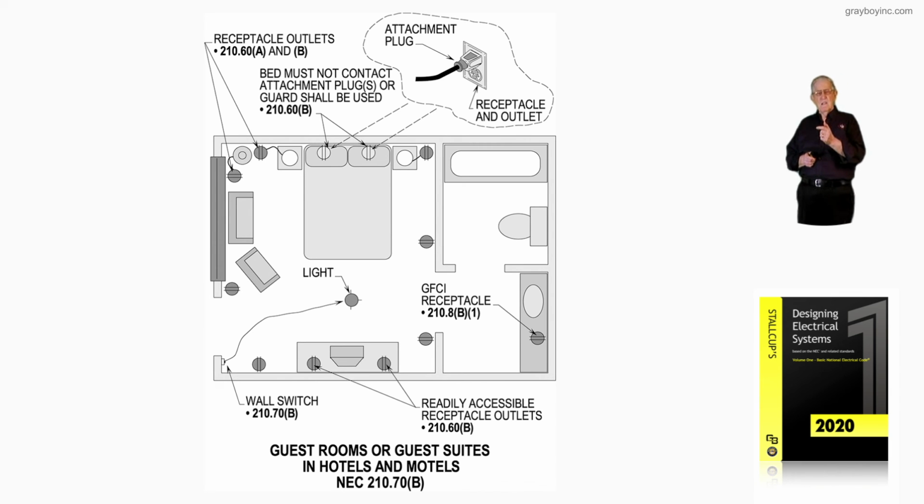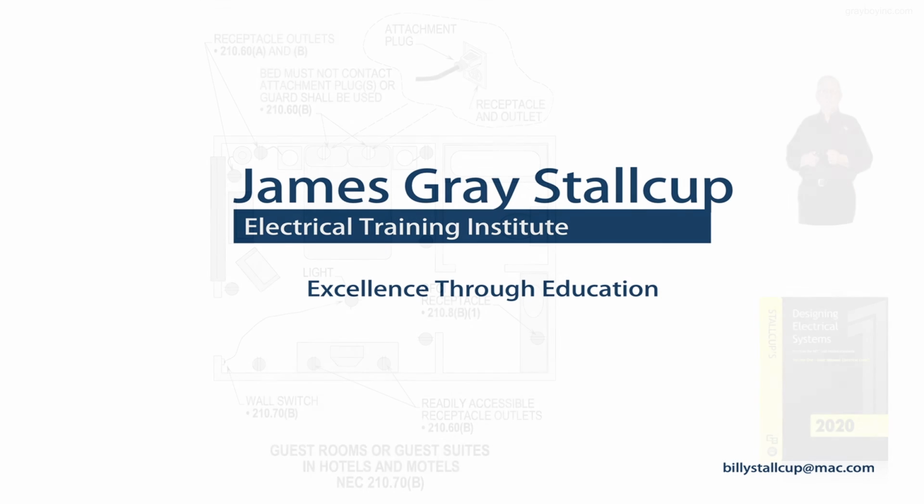But you would be then with the receptacle requirements in there where, by the sink and basin, where grooming tools would be plugged in, such as hair dryers and other things that the ladies may be using. And then notice 210.8(B)(1) would require that to be GFCI protected.